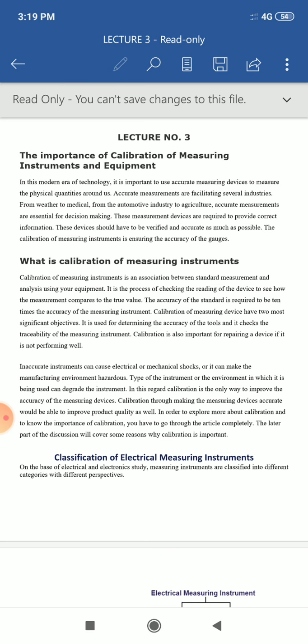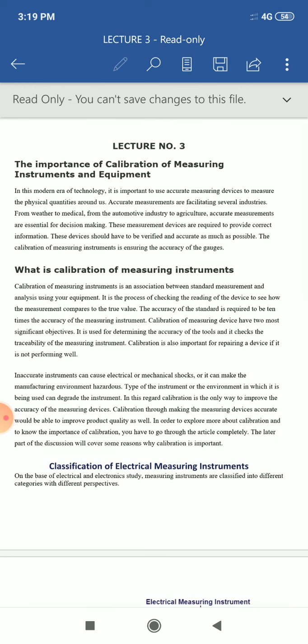The calibration of measuring instruments ensures the accuracy of the gauges. Now, what is the calibration of measuring instruments? Calibration of a measuring instrument is an association between a standard measurement and the analysis using your equipment. It is the process of checking the reading of the device to see how the measurement compares to the true value. The accuracy of the standard is required to be 10 times the accuracy of the measuring instrument.